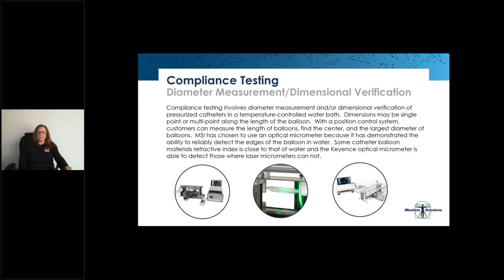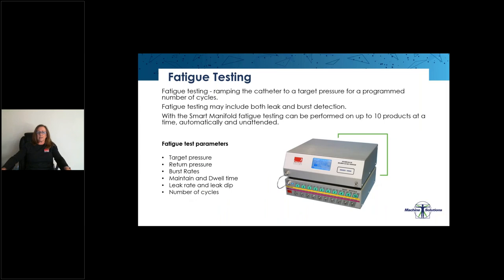Fatigue testing involves ramping the catheter to a target pressure for a programmed number of cycles. Fatigue testing may include both leak and burst detection. And with a smart manifold, fatigue testing can be performed on up to 10 products at a time, automatically and unattended by an operator.